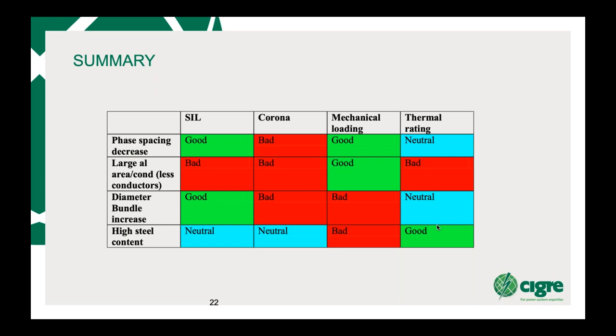So that's really how you can see that there is no one line which has got all green. And this is a problem because you now need to choose. You've got two greens here, so maybe decrease the phase spacing. That might be quite good, and this is why compact lines are so popular. But it's bad for corona, so you need to actually try and manage the corona within the compact line design.